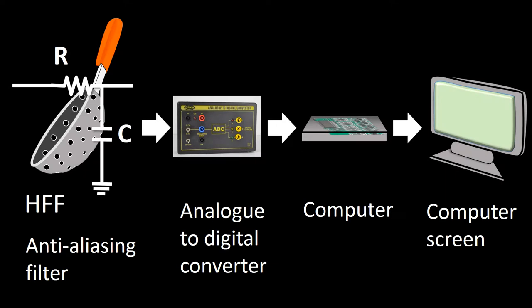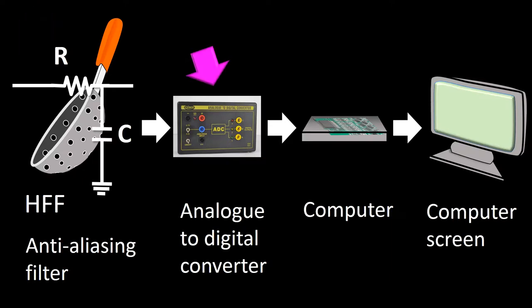The process of electrical brain wave registration on the computer screen starts with an anti-aliasing filter. This filter is an analog high frequency filter, usually with a cutoff of 100 Hz, solidly built into the machine by the manufacturer. From the anti-aliasing filter, the analog activity goes to the analog to digital converter, where the incoming analog signal is transformed into numerical values. This is done by intermittently capturing samples from the analog signal at specific intervals and assigning them a binary number.